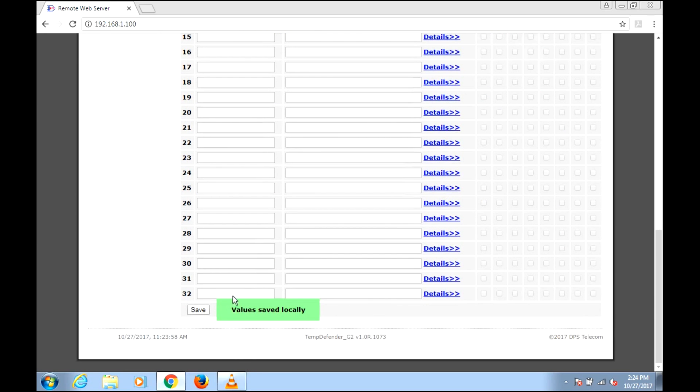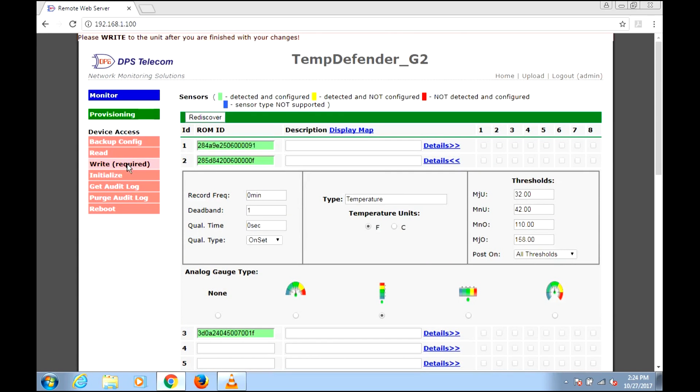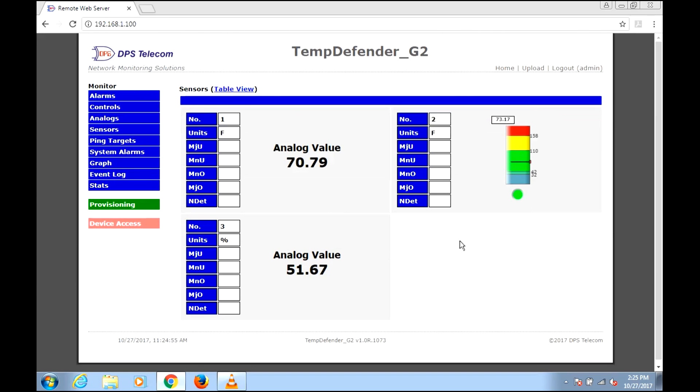We save and write to the unit to save these settings changes, and it's been saved. Now we can go over to Monitor. You'll see the internal temperature sensor wasn't configured with a gauge, so it's just a numerical value. The gauge here is for temperature. In this room it's room temperature at about 73 degrees, putting us in the green zone — not at any of our threshold values. The humidity sensor is currently reading 51.67.